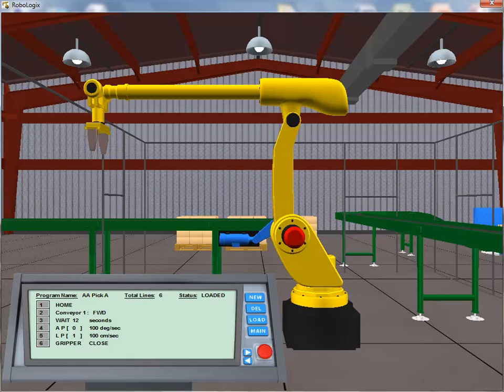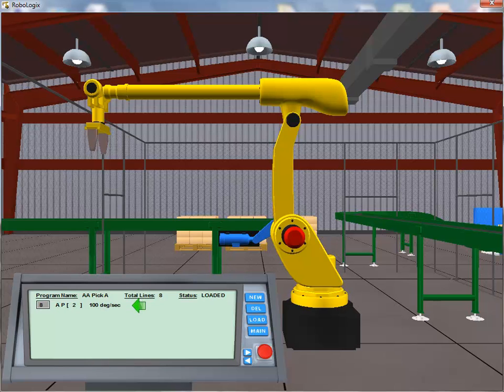In this way, we'll continue on adding the instructions to move the tool center point to the desired location or pick up or drop the box as needed. The next instruction to be added is a Linear Motion instruction. We reference index 0 as that's the location directly above Conveyor 1 — this instruction will lift the box above the conveyor. We then add another Angular Motion instruction to pivot the arm over top of Conveyor 2, using a new reference index number for the position register, as this is a unique and separate position.